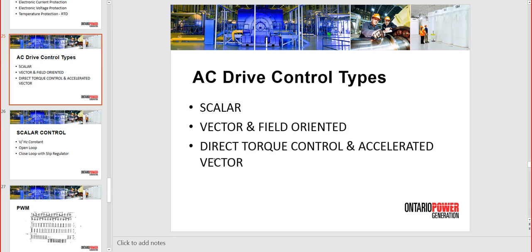Not everybody provides direct torque control. For instance, SEW Eurodrive, Movitrac has vector and scalar, but does not offer direct torque control drives. Direct torque control you can find from Siemens, Mitsubishi, Toshiba, Danfoss, even Schneider, they have direct torque control, GE. So all the big manufacturers, they will have all three. So if you order a direct torque control drive, you will have all three, because it's like building one on top of the other. So direct torque control will have vector control and scalar.